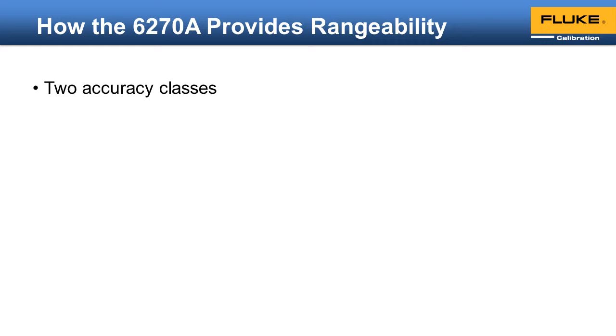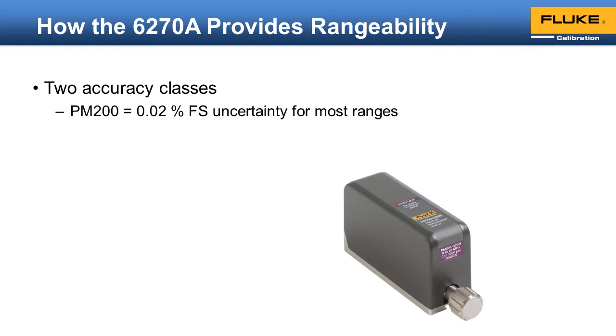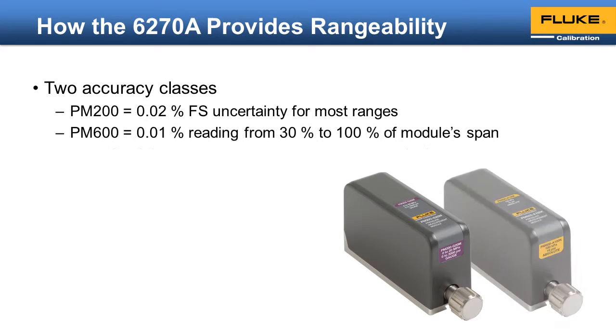The 6270A offers two different accuracy classes and a variety of pressure ranges. The PM200 provides a one-year specification of 0.02% full scale for most ranges, whereas the PM600 class provides a one-year specification of 0.01% of reading for 70% of its span. This provides an unsurpassed level of rangeability.